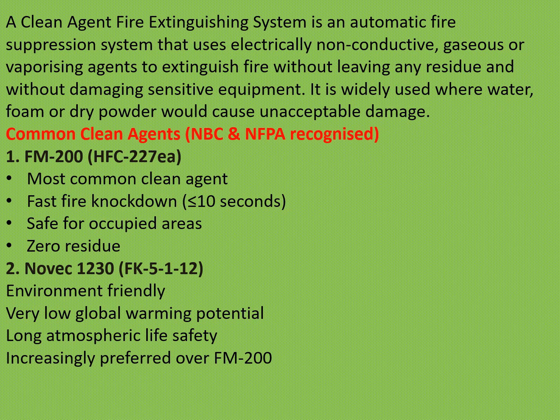The second important clean agent is Novec 1230, in bracket known as FK-5-1-12. The properties are it is environment friendly, very low global warming potential, long atmospheric life, safety, and the fourth advantage is that it is increasingly preferred over FM 200 because FM 200 has global warming potential.